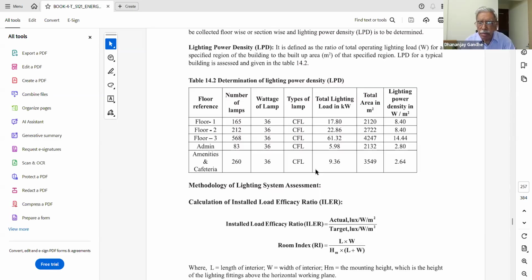The fourth area is the admin system, where the lighting load works out to 5.98 kilowatt. And the fifth area, amenities, the lighting load works out to 9.36. So these are the total wattages, the total kilowatt load in each floor that is mentioned over here. The total area of each floor is mentioned here. Obviously, floors 1 and 2 are mentioned.